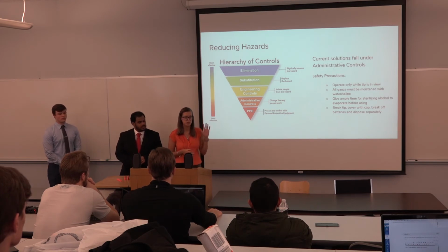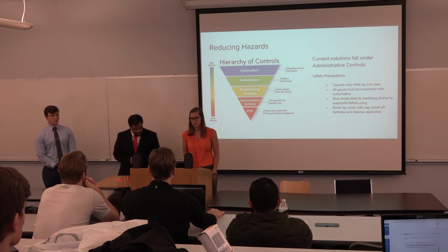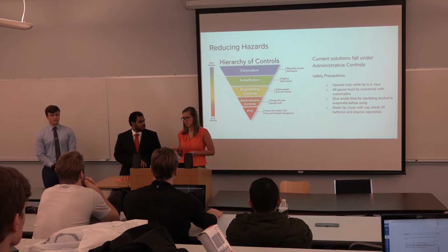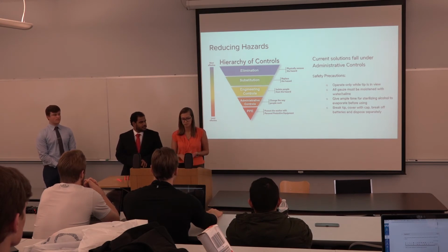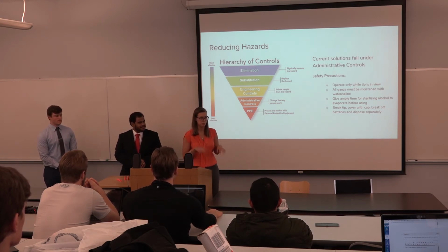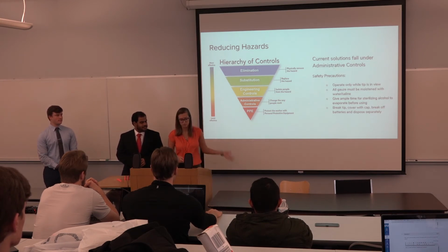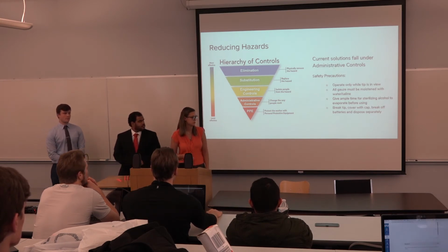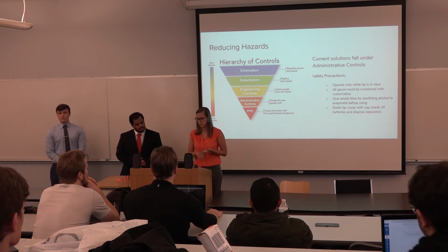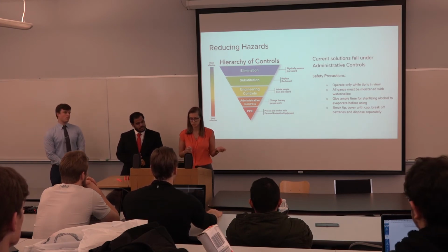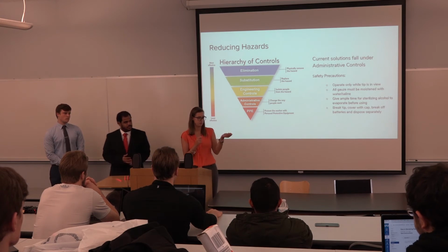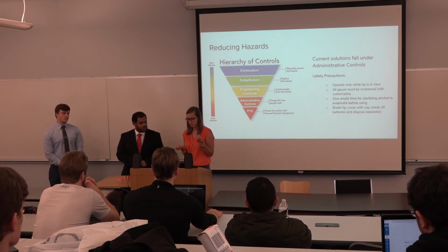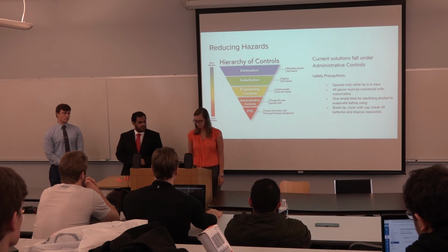So they give a long list of safety precautions to take. You're not supposed to turn it on unless you're looking directly at where the tip is pointing. Any gauze should be wet down so that there's less risk of it catching fire. Like I said, the alcohol is going to be given time to evaporate before use. And then as you're throwing them away, you're supposed to break the end of the tip off, remove the batteries if you can, and then recap it so that no fires start in garbage cans.